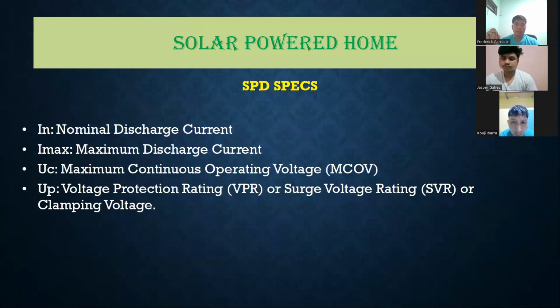Of course, we now have the SPD specs. The In is the nominal discharge current. This is where the SPD will be living most of its life, the expected amount of current it will normally be discharging. The maximum current, the Imax. The UC, the maximum continuous operating voltage. The UP, the voltage protection rating, VPR, or surge voltage rating, or clamping voltage.